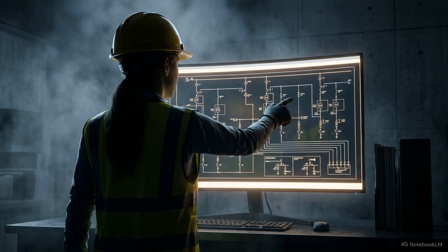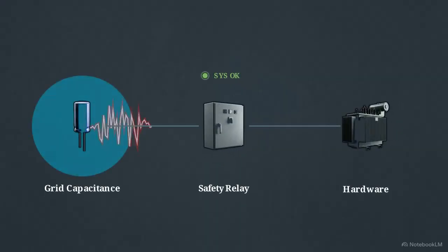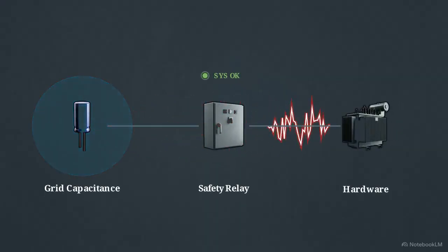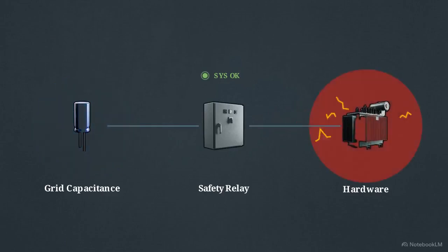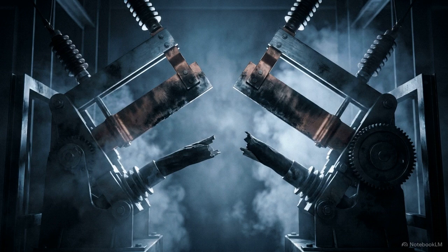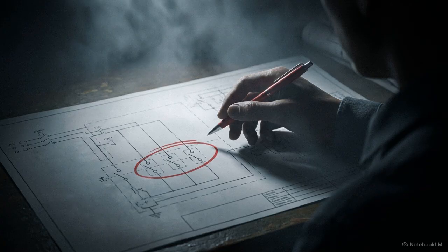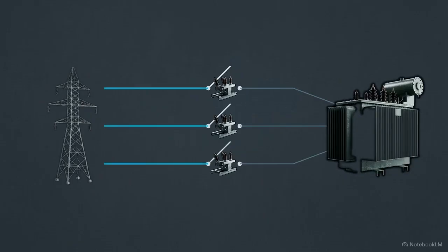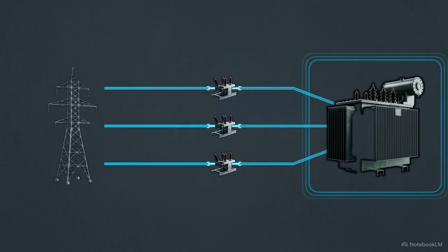This is why engineers treat this transient with such caution. It turns the grid's own natural energy storage against its most expensive hardware, bypassing the standard safety nets designed to protect them. To stop the destruction, operators have to actively break the mathematical loop and force the electrical parameters back into a stable state. The best defense is strictly operational. Grid planners design careful three-phase switching sequences to guarantee an unloaded transformer is never left isolated in an energized, highly capacitive circuit to begin with.